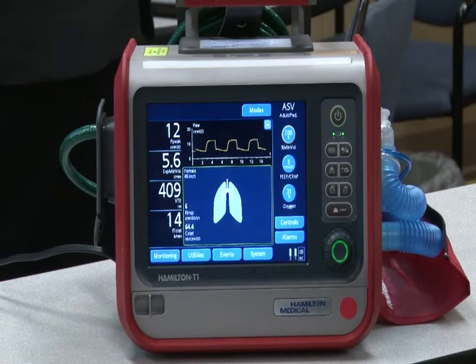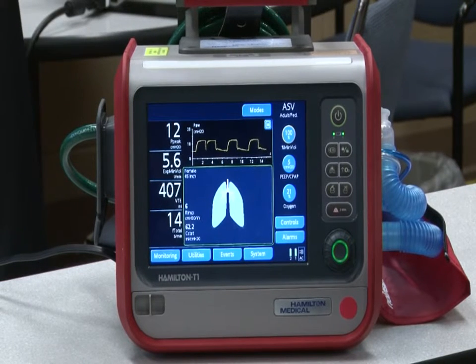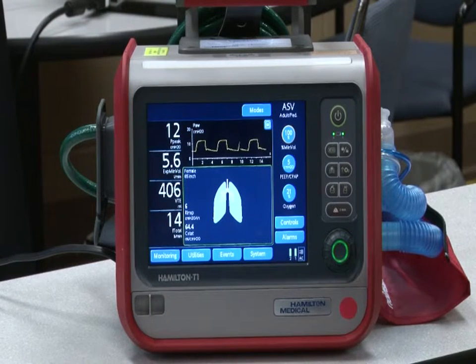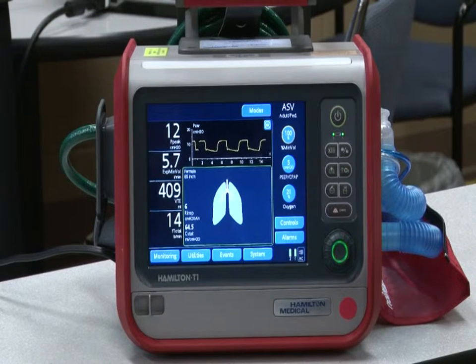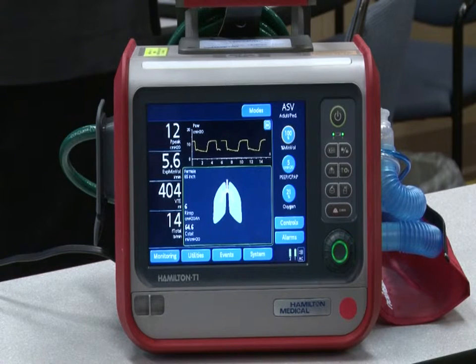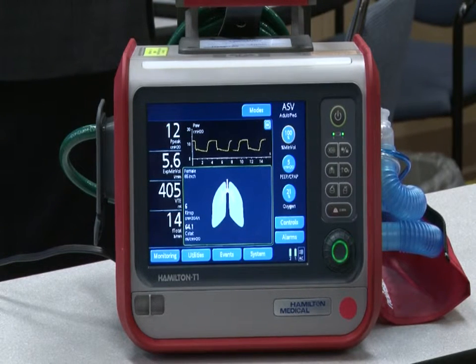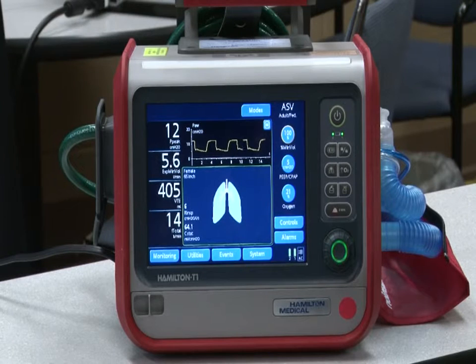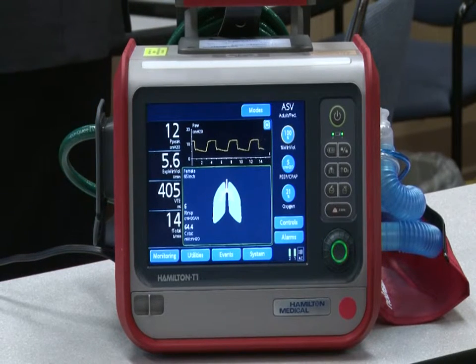This is awesome because you can see it large. This has a normal shaped lung, normal looking airway. That's the static compliance and that's the airway resistance, and those are measured breath by breath from the ventilator, and that information is available by virtue of the flow sensor. And then the ventilator, because we indexed the ventilator and the patient together, didn't we? We put in the gender and the height, which calculated the ideal body weight. So not only does it measure the compliance and the resistance, but it says, how does that compare to a patient of that gender and ideal body weight? Is it normal or abnormal?